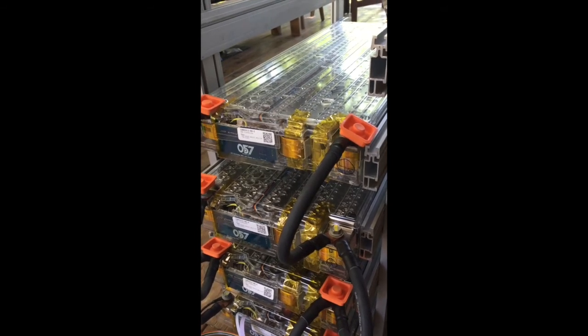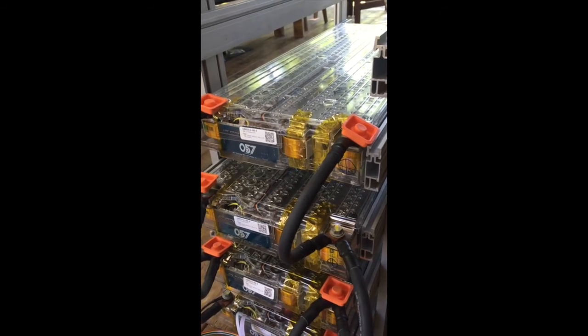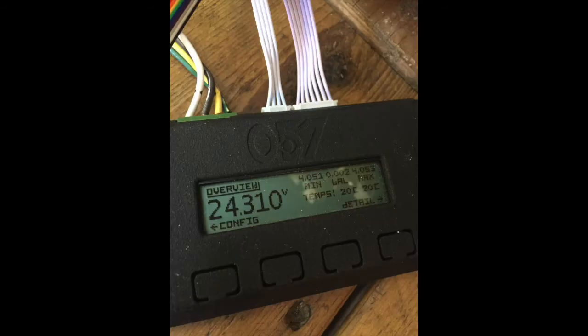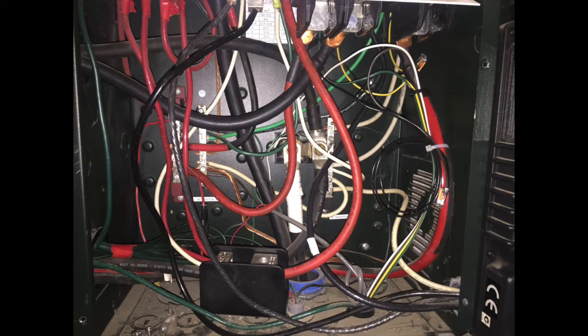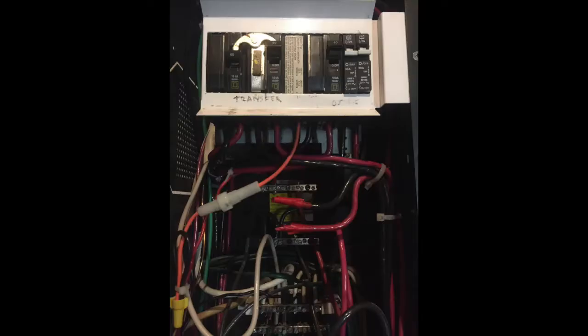This became a problem for the inverter when using a generator to charge the batteries instead of solar. The lowest voltage setting on the inverter-based charger is higher than what the batteries want to see. This means that an external control is required to turn off the charger. Fortunately, that can be handled through the BMS.